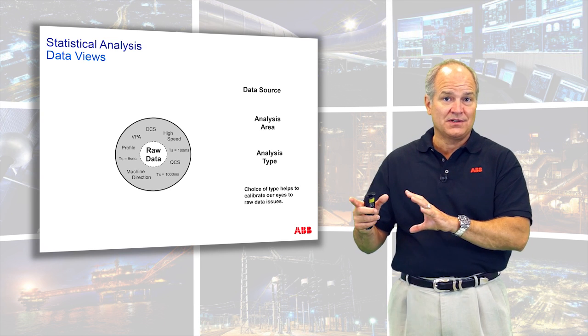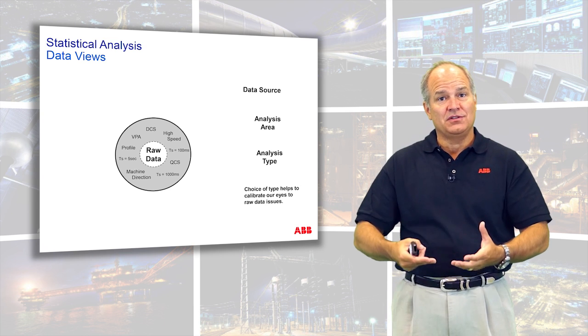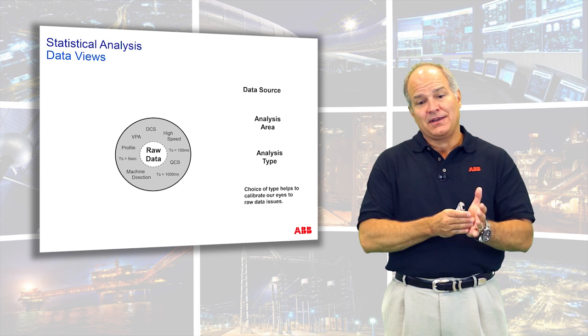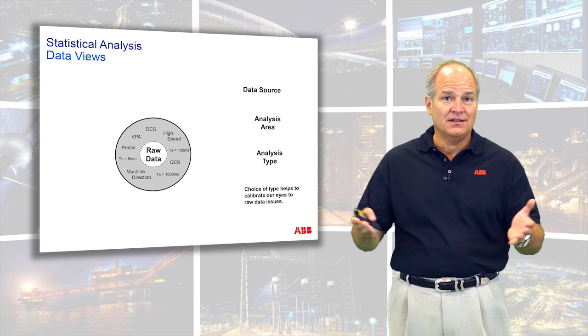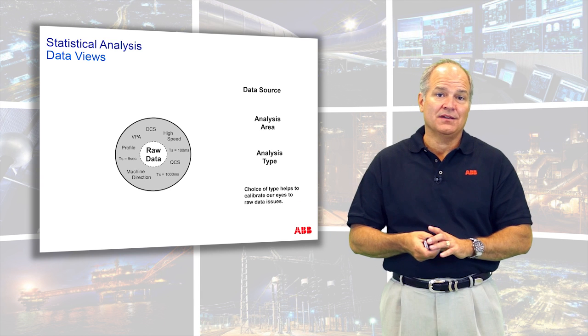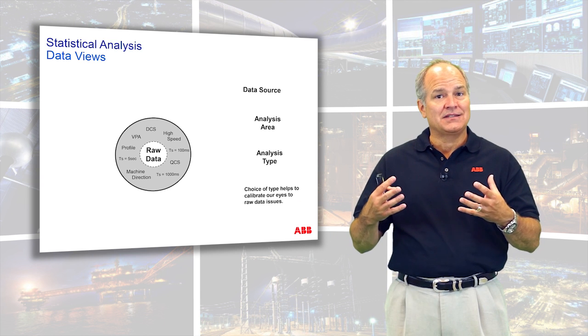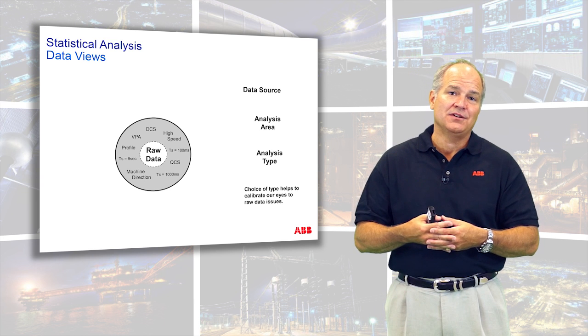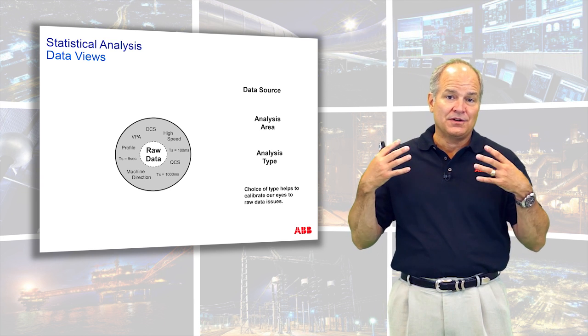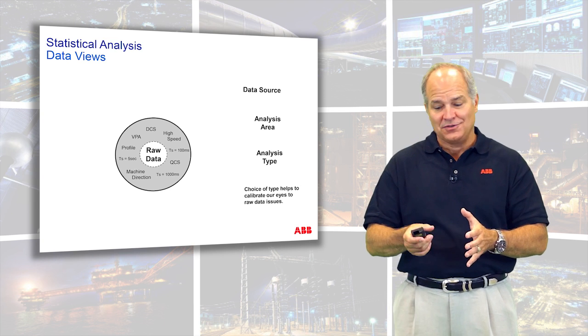That's a whole other subject. But I wanted to at least alert you to the fact that, let's say you're sampling every hour and you have a problem that's happening every 10 seconds. You'll never see it. Actually, it'll alias into something else. So I'm just bringing that up, that statistics are functions of the resolution of the information that you're loading into it. And we're going to assume in this one that we've got the right resolution.